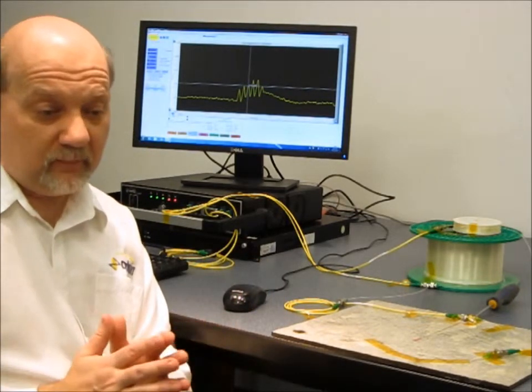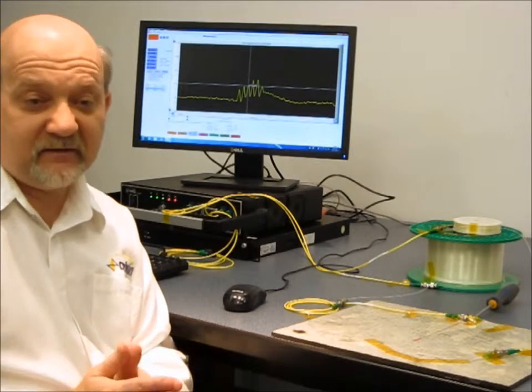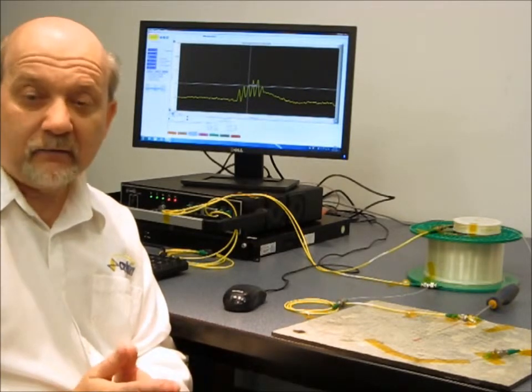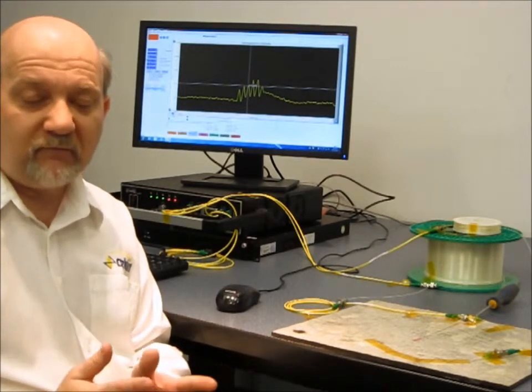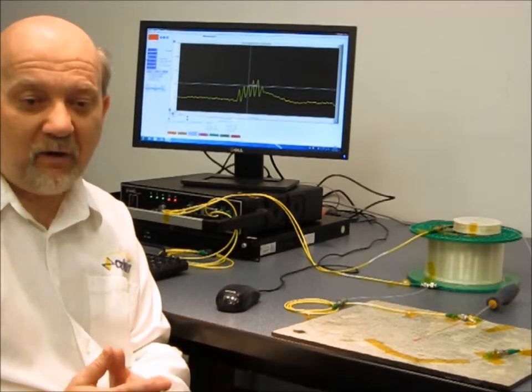Even though we've induced changes in a section that's less than a millimeter wide, and even though our spatial resolution is set to 10 centimeters, these events are quite obvious on the instrument. And this is what makes the DSTS instrument such a valuable tool for monitoring, for detecting the development of cracks within a structure such as a dam, a bridge, or roadway.